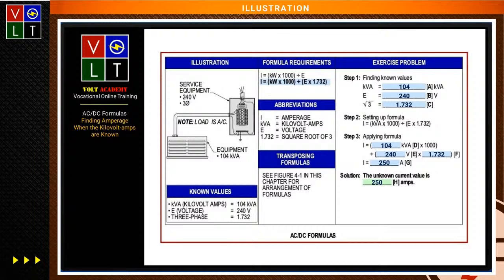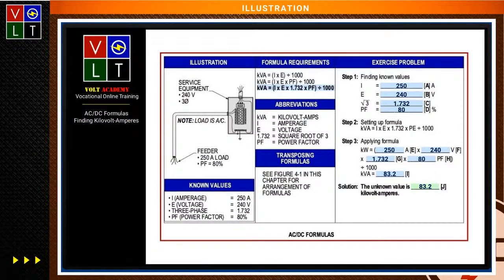And when we get over and we start looking at applying Ohm's law and doing pi formulas and combining them, I'm going to use all the same values through there, and you're going to see we're going to get the same exact value when we apply that calculation. Right. All right. Now, kind of like a cookie cutter. Sure. Now, look at this. Now you've got 250 amps, 240 volts, 1.732 for the three-phase, and 80% power factor. Now, I'm going to take it back to put it in kilovolt amps.